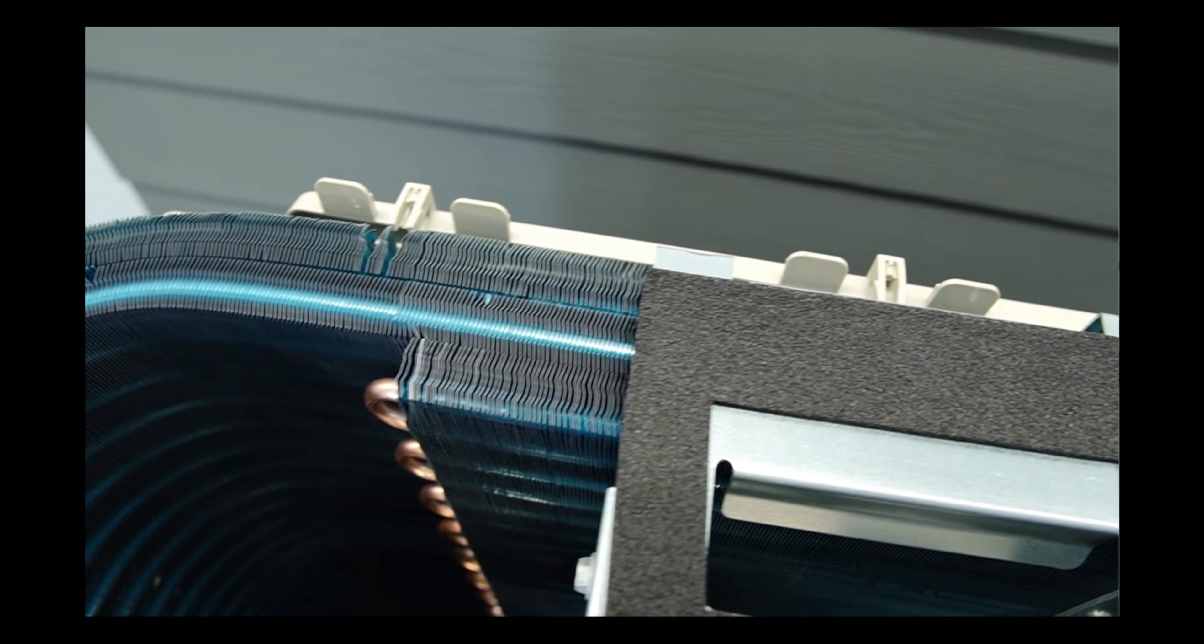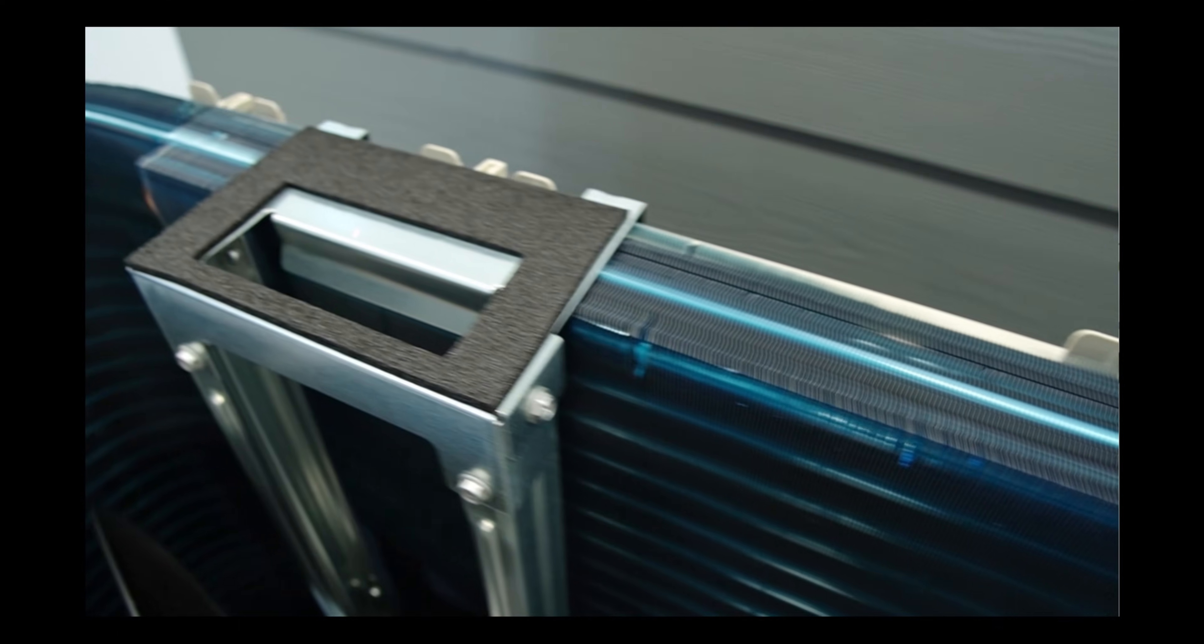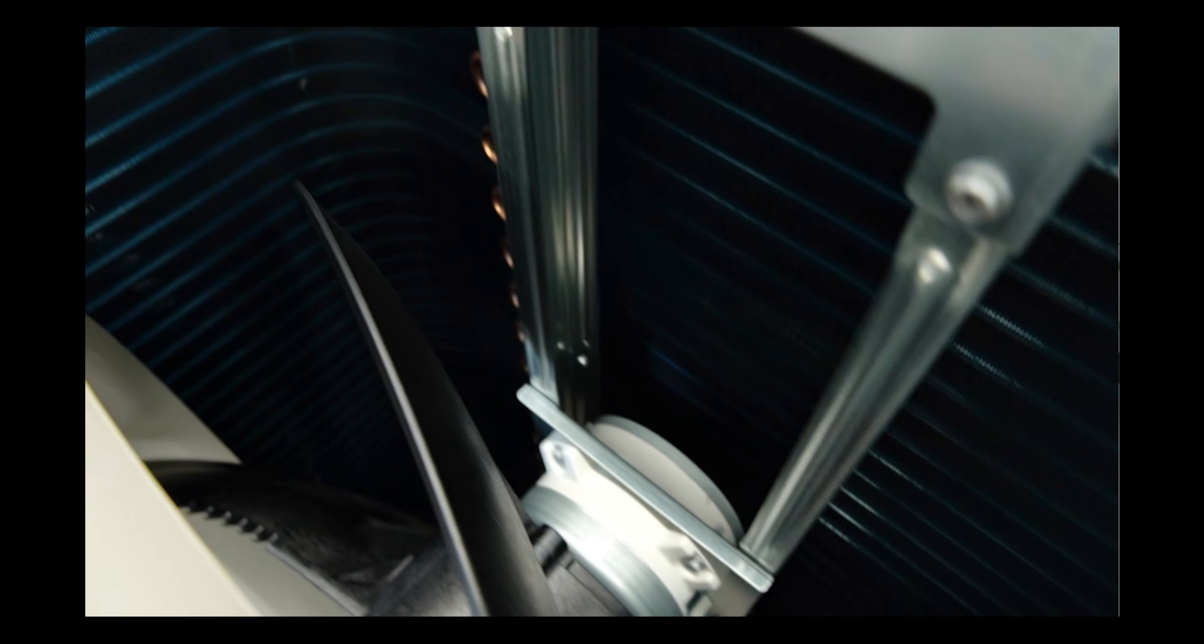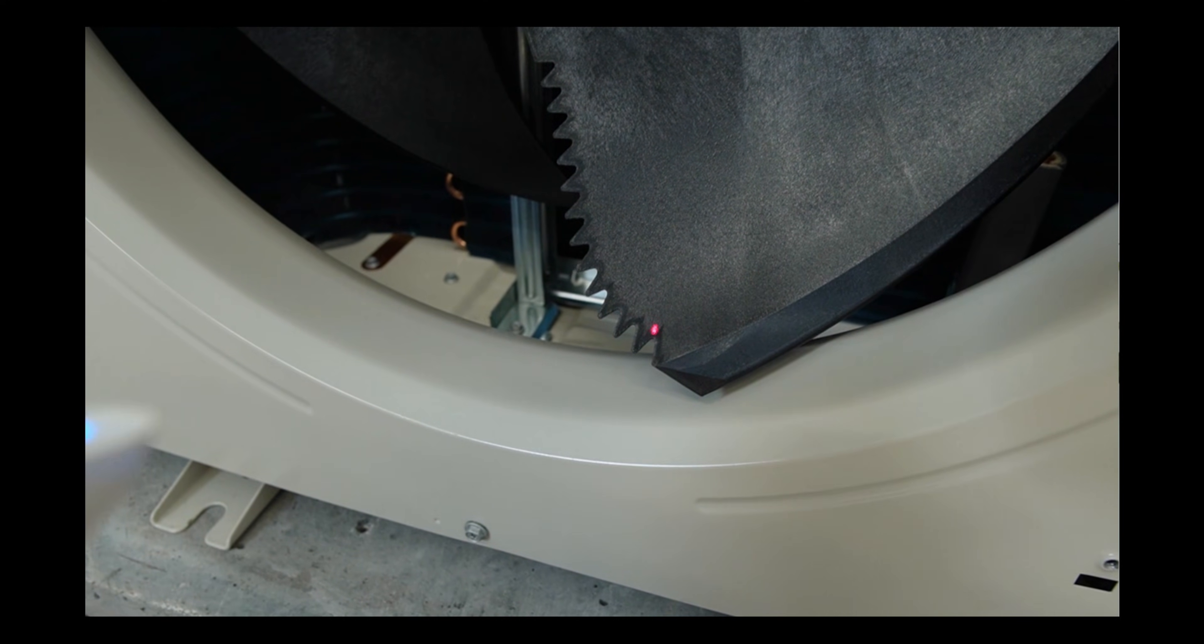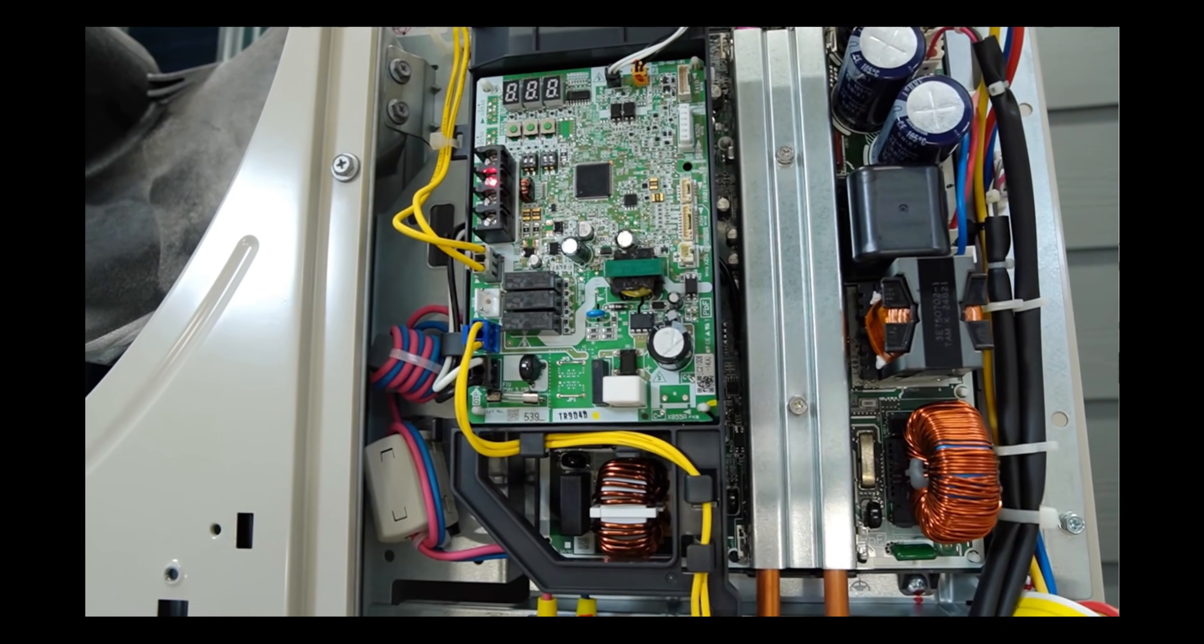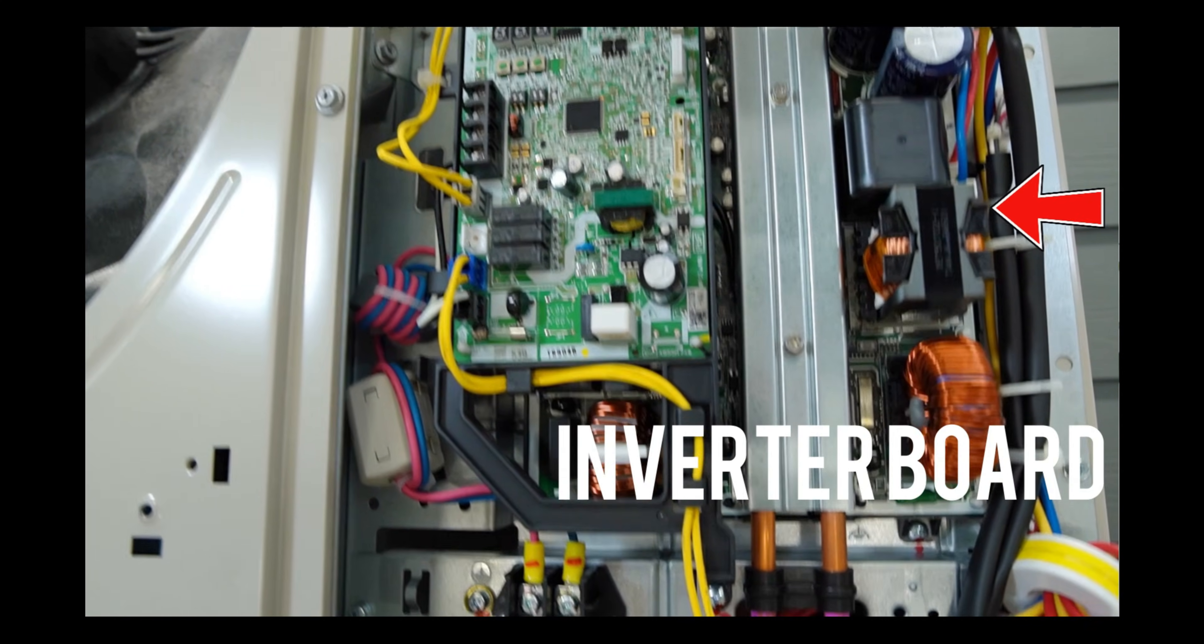Now let's start with the coil. As you can see, this coil is a monster. They added an extra layer, which is clearly visible here. There are two unusually large fans with epoxy sealed brushless fan motors. These fan blades have notches on the leading edge to make them quieter. We've got a huge reversing valve here. There are also two boards. The boards are separated.